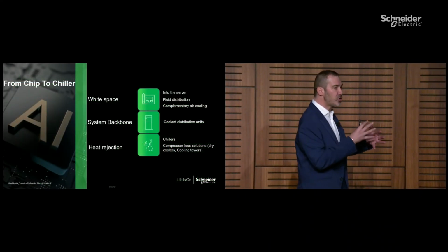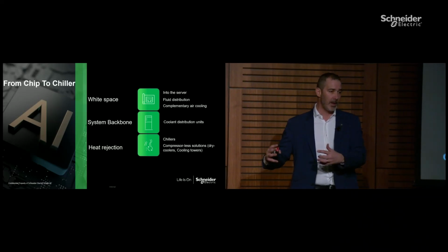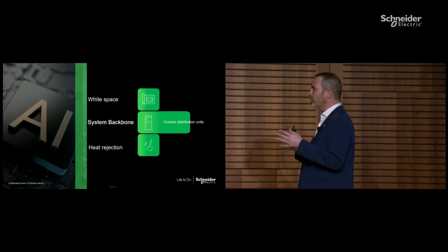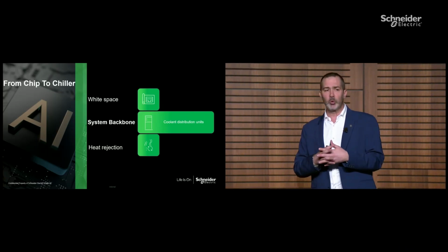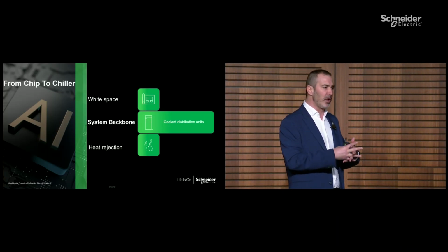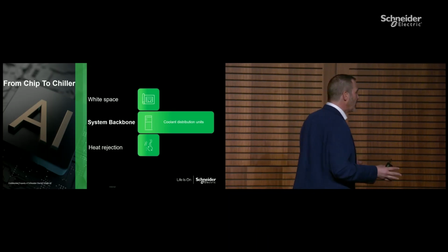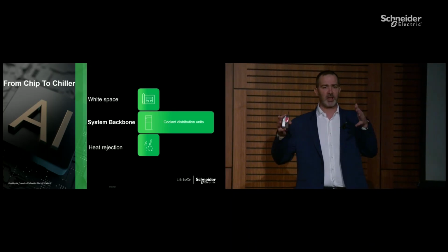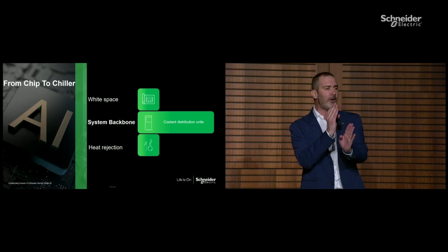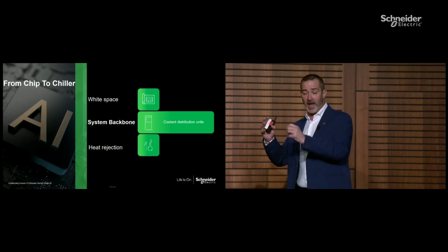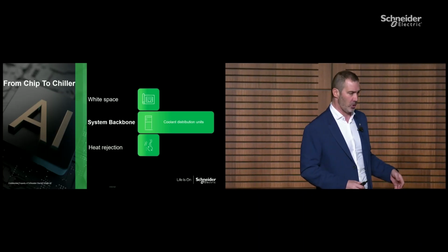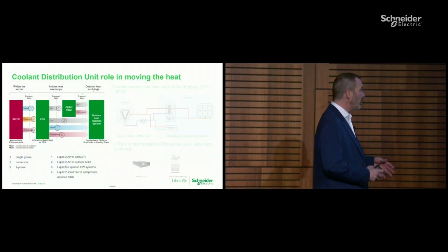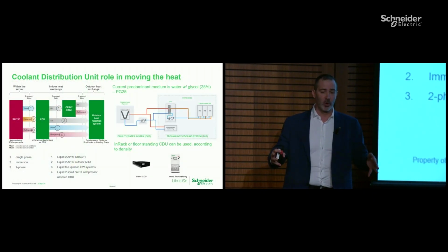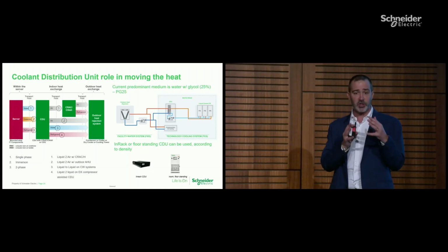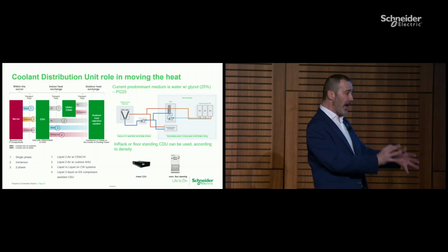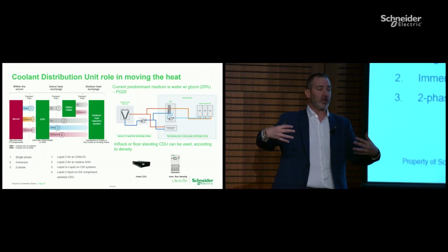Moving out from the data hall, in this journey from the chip to the chiller, certainly one area that we need to consider is what is in between, what is the backbone of the liquid cooling infrastructure. And we can argue that all of those are essential devices. However, the backbone, the interface between the liquid cool server and the heat rejection units is the coolant distribution unit. The CDU, and we can argue that there are plenty of different CDUs, but from a very high-level perspective, the CDU is that device that allows the connection from the server to the heat rejection.